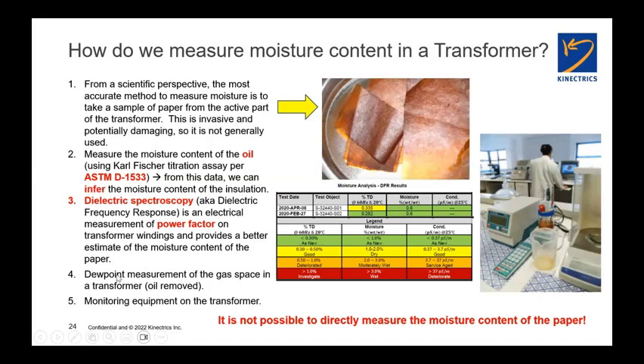When we're processing transformers, drying them out, and we have the oil removed, what we would normally do at that point is a dew point measurement of the gas space. You have to wait for thermochemical equilibrium to take place, which is typically about 24 hours for a big transformer. Then you take a sample of the gas space inside the tank and measure the dew point of that. Using something called a Piper curve, you can get the moisture content of the paper inside the transformer. So these are all indirect methods, is the point.